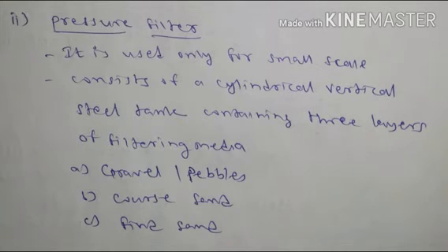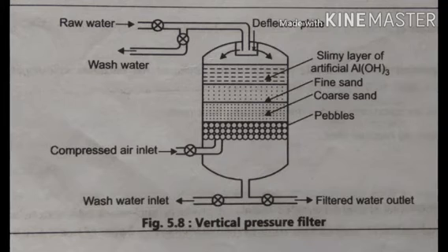In the case of a pressure filter, water under pressure is forced up from the tank, which removes the matter that has clogged the sand pores. The backwash water is then allowed to go to the drains. Nowadays compressed air is used to agitate the sand before the backwashing.